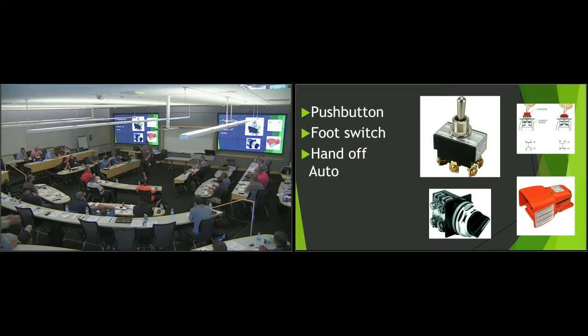The foot switch down there on the right, typically in my local, since we do a little bit of pulling, is a safety device. If you do not have a foot switch connected up to your tugger, you'll be like that guy with that thing whacking you, and the whole tugger will rip up, and you'll have no way of unplugging it.